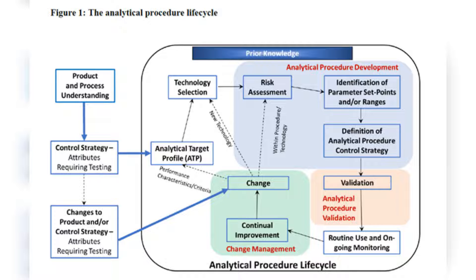The guideline's Figure 1 depicts the analytical procedure lifecycle, highlighting development, change management, and ICH Q2-covered validation. Elements vary by intended use and approach, with potential concurrent occurrences. The analytical target profile (ATP), influenced by the quality target product profile, is vital for procedure development, determining necessary attributes and performance criteria. ATP guides technology selection, procedure design, and continual improvement, ensuring long-term suitability. Annex A provides ATP examples.